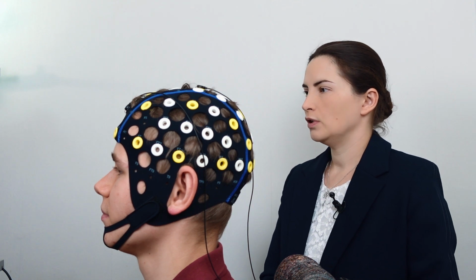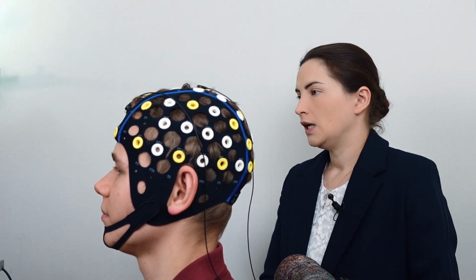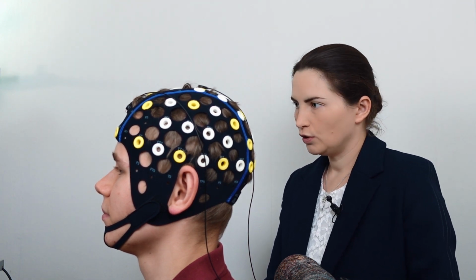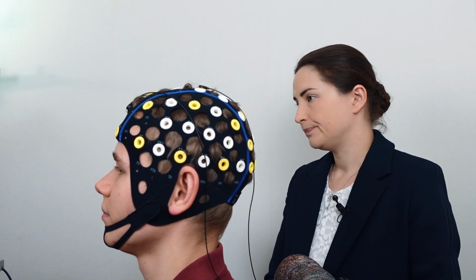In this case, we need to carefully check all the procedures we have just performed. Perhaps there is hair left under the electrode, or the skin has not been treated well enough with a scrub, or not enough gel. We need to add it in this case. As soon as the color changes to green, you can move on to the next steps. Similarly, we set up all the other electrodes.